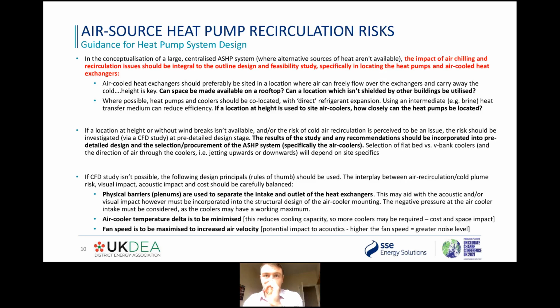On key design considerations: if you can't do a CFD study, or don't have time to investigate, here are some rules of thumb. Always put a physical barrier between the intake and outlet of the heat exchangers to stop recirculation. Always minimise your air cooler temperature delta by putting in as many air coolers as is technically feasible, with as low a temperature delta as possible, and increase your fan speed as much as possible to increase ejection air velocity from the air-cooled heat exchangers.